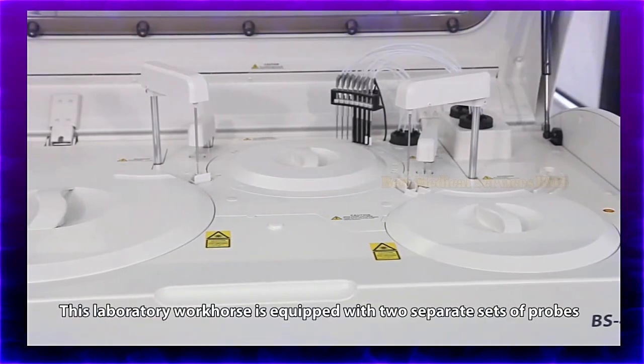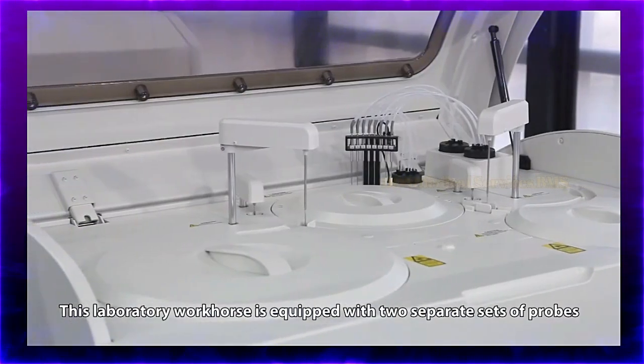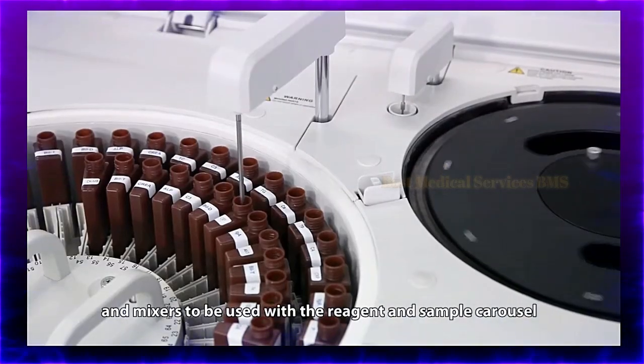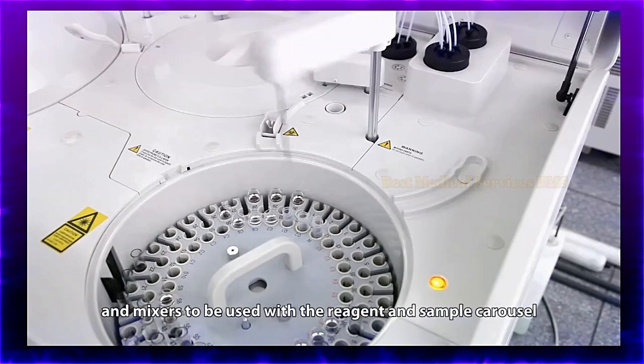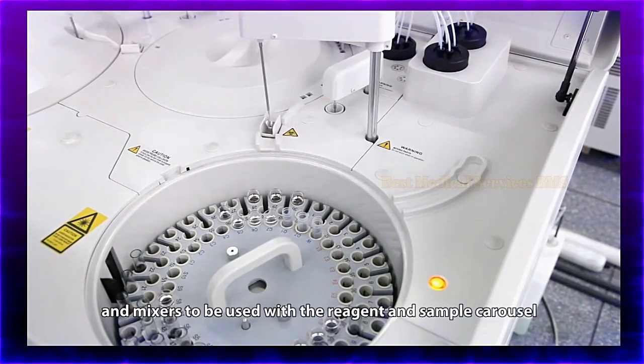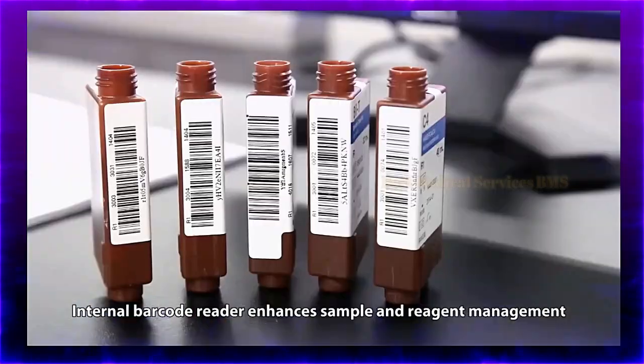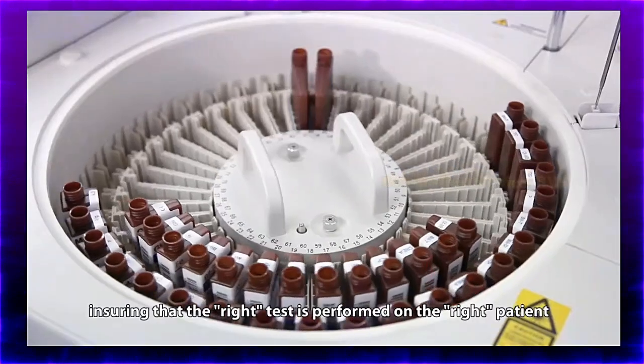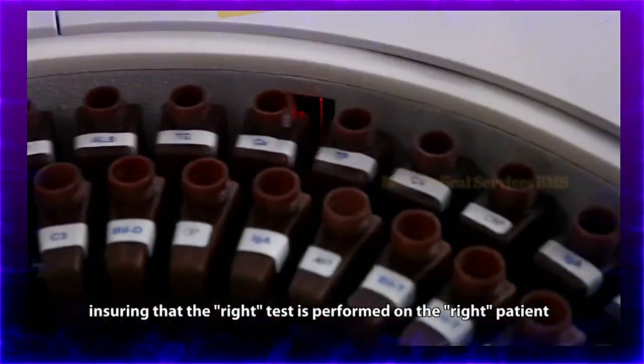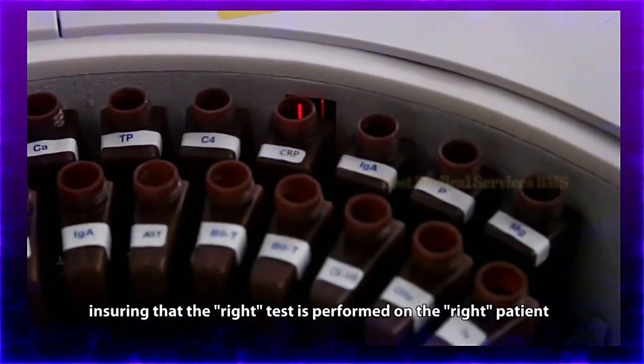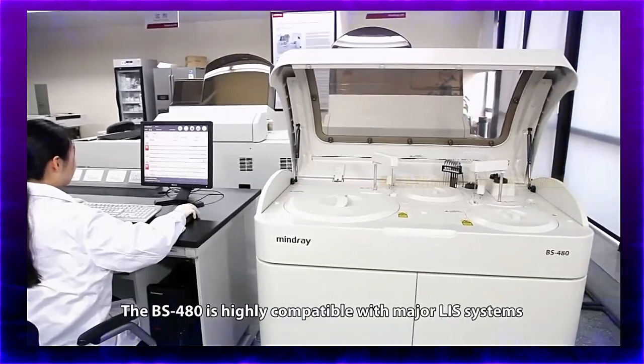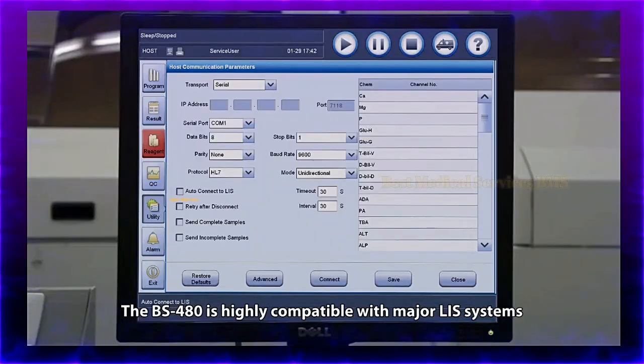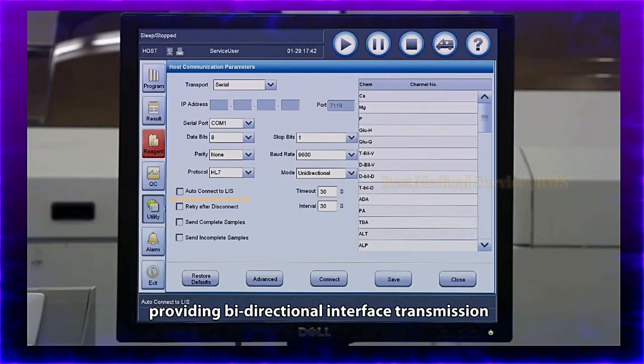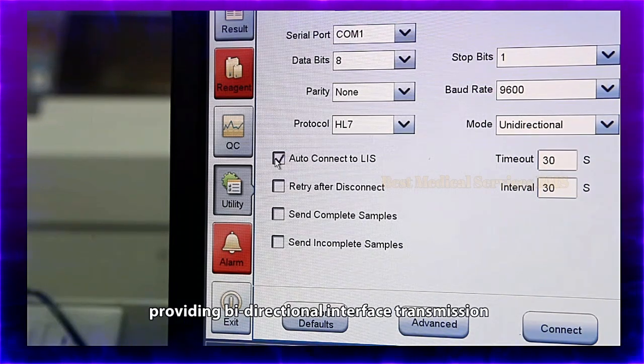This laboratory workhorse is equipped with 2 separate sets of probes and mixers to be used with the reagent and sample carousel. The internal barcode reader enhances sample and reagent management, ensuring that the right test is performed on the right patient. The BS-480 is highly compatible with major LIS systems, providing bidirectional interface transmission.